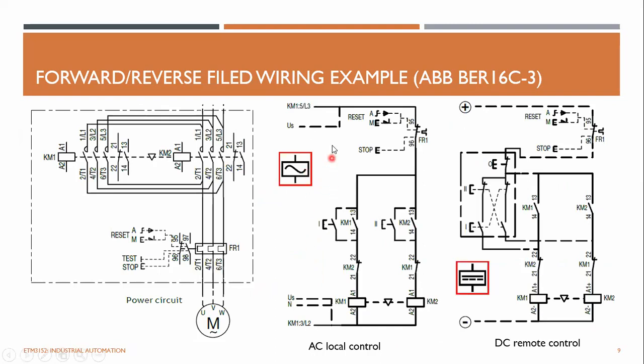And this is a real field wiring example, ABB BER16C-3. And this is what you call the AC local control, which means the controlling is done very close to the motor. And this is a DC remote control. You can control remotely using a PLC. So the wiring is done using DC wiring. And this is the AC wiring for local control.